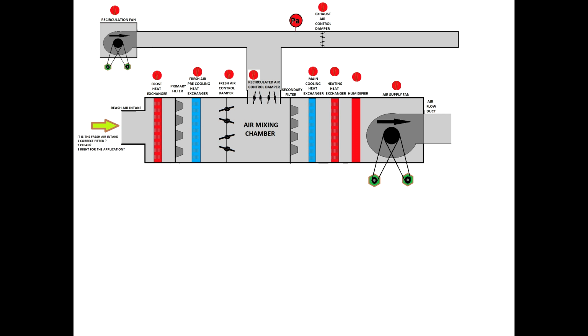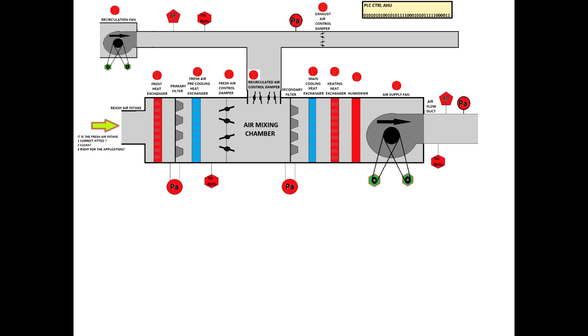It doesn't matter. So if everything is okay, you start putting probes into the system. Across the filters, you'll put analog differential pressure sensors connected to the PLC, so you can read the filter contamination level. Into the ducts, you'll put pressure switches, air volume probes, and also relative humidity and temperature probes. You have to control the air pressure, the air volume, and also the temperature and the relative humidity. Then you can start the system.